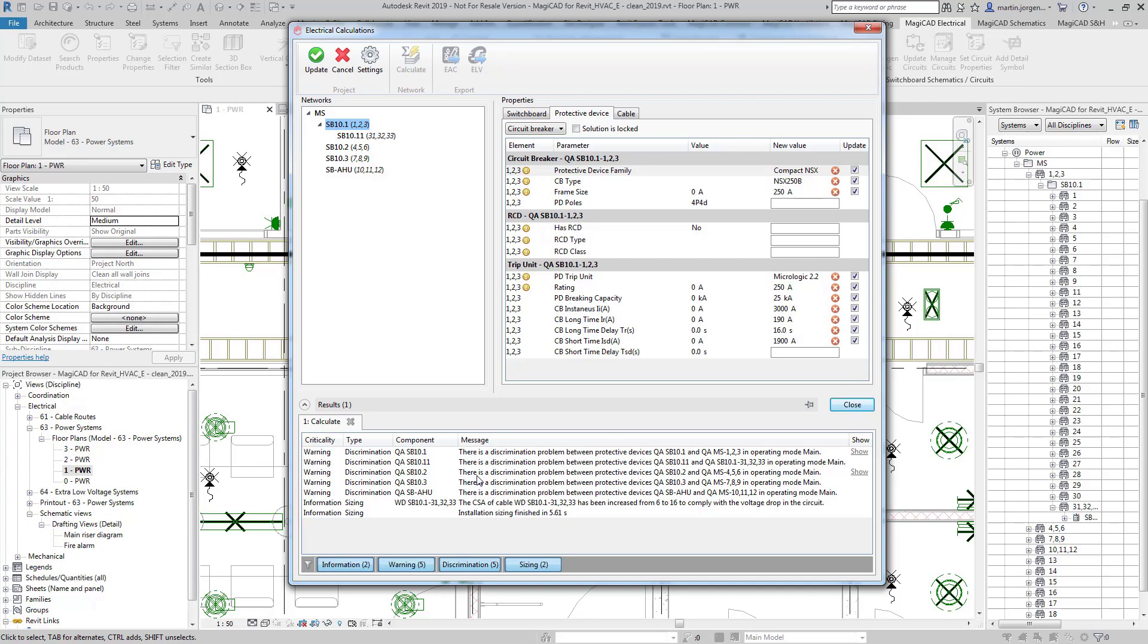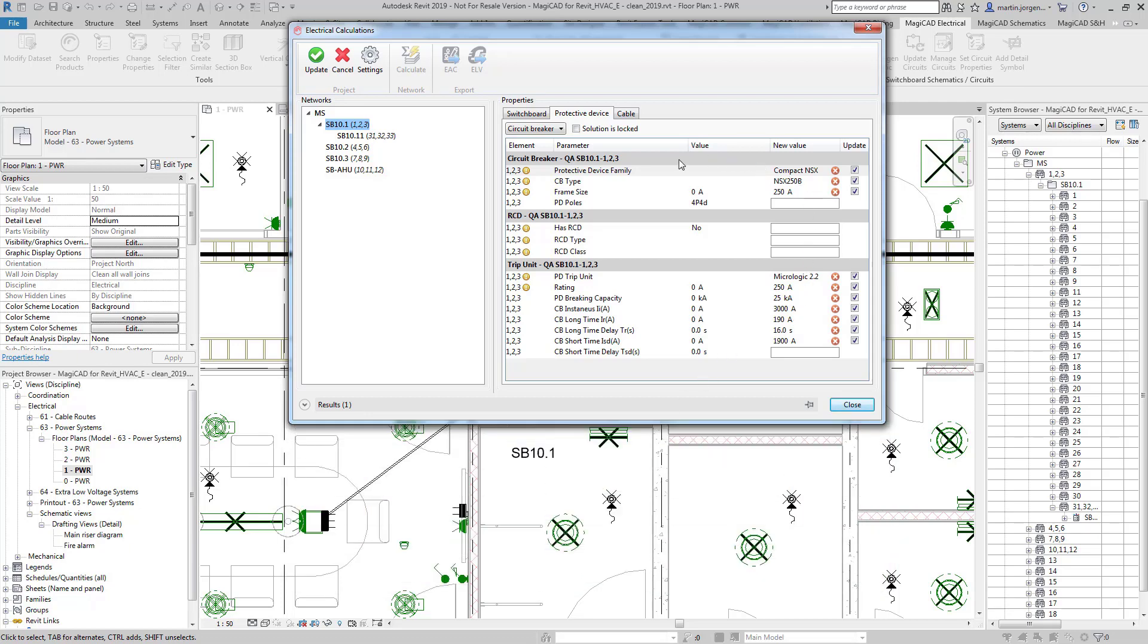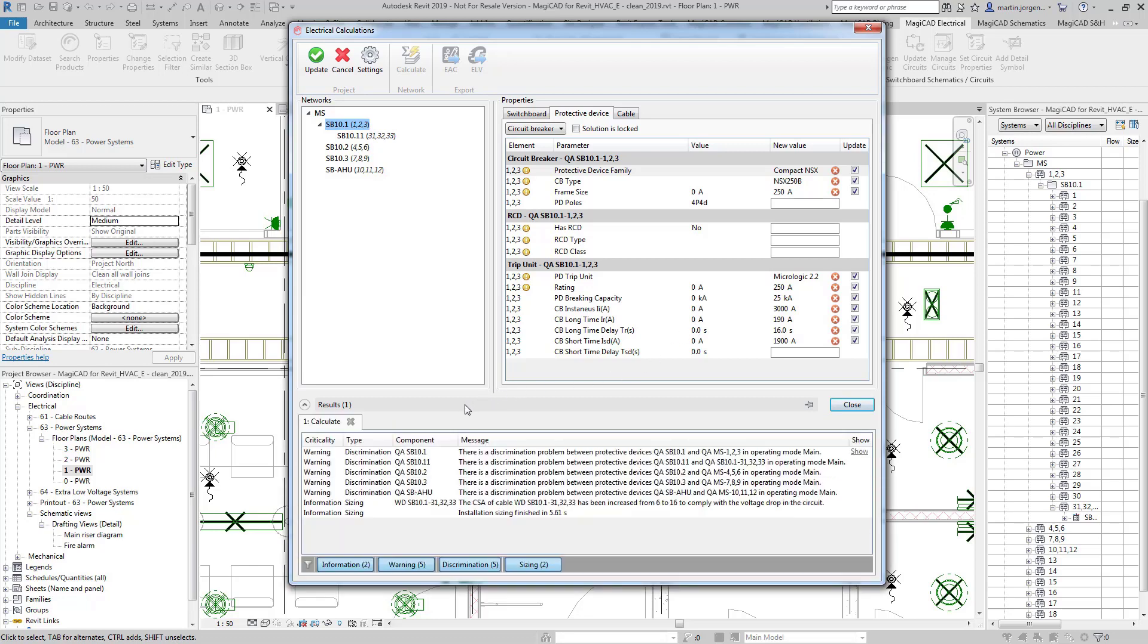So with this we can also see here that we have a CSA of a cable which has been increased from 6 mil to 16 mil to comply with volt drop in the circuit.